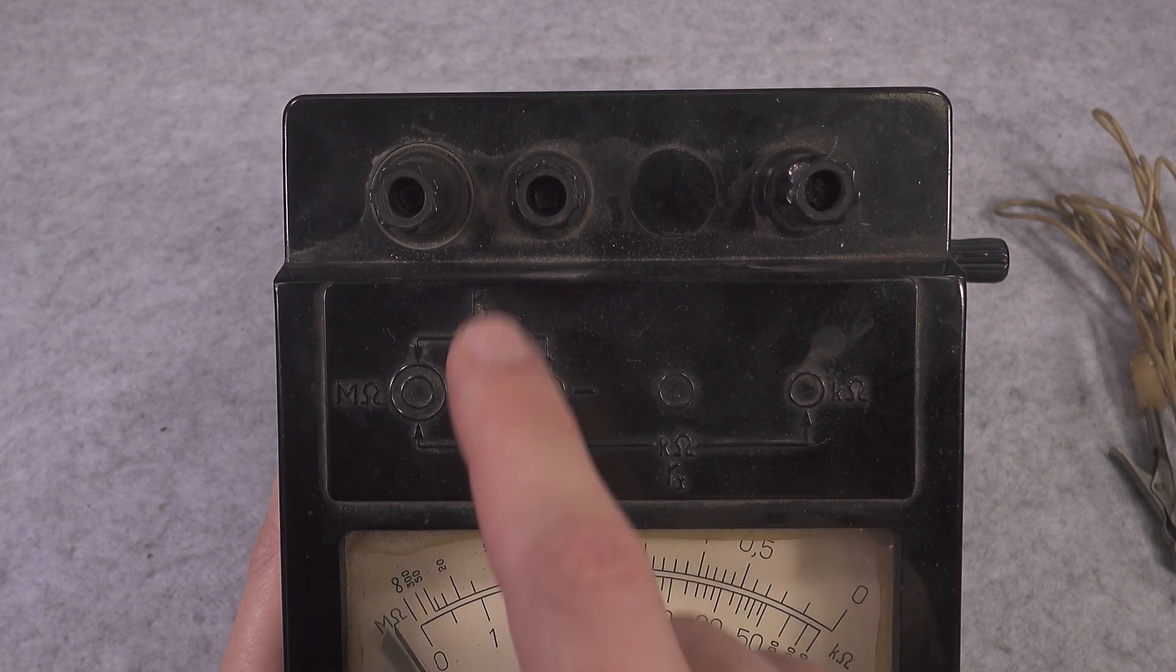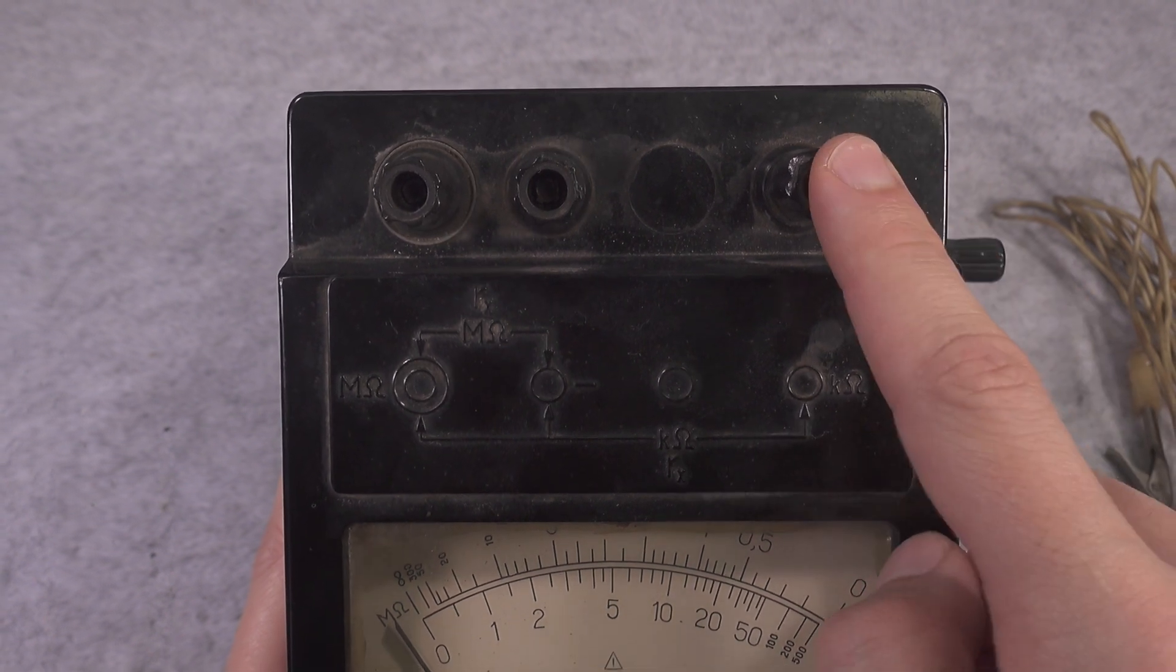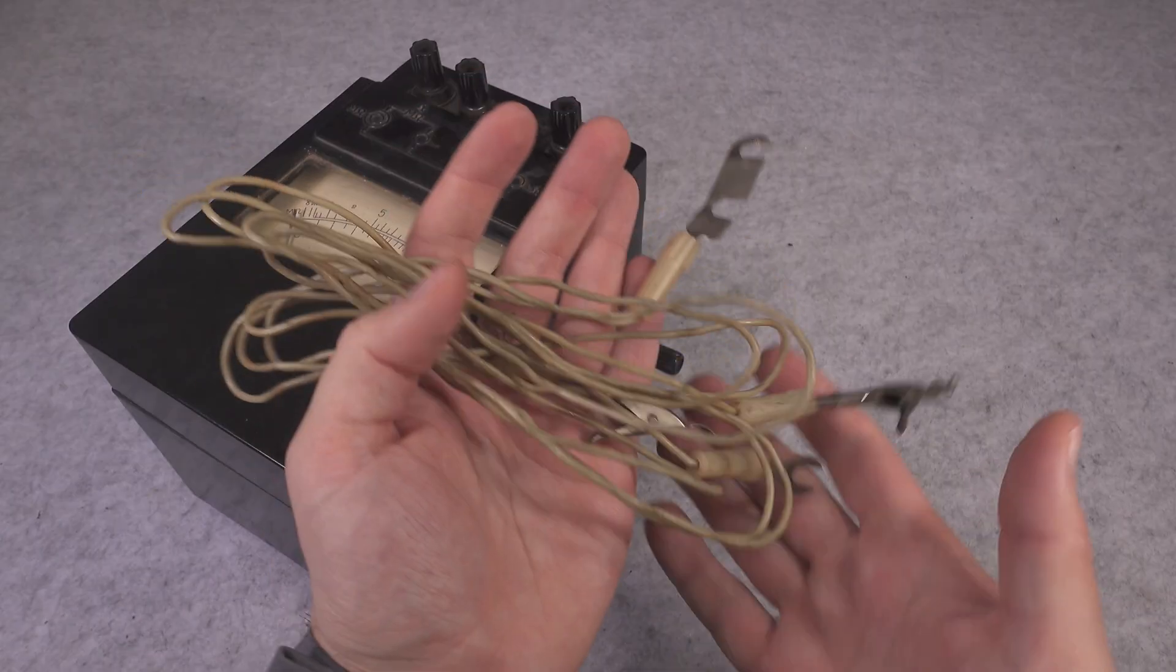You need to apply your load into two combinations of those terminals. If we would like to measure mega ohms, then we are going to attach our resistance between those two blocks. But if we would like to measure kilo ohms, then we need to bridge those banana sockets together.